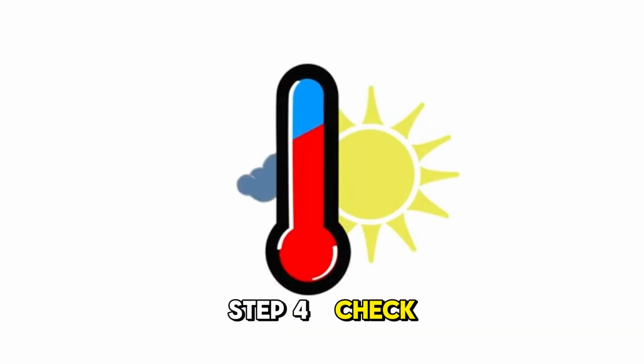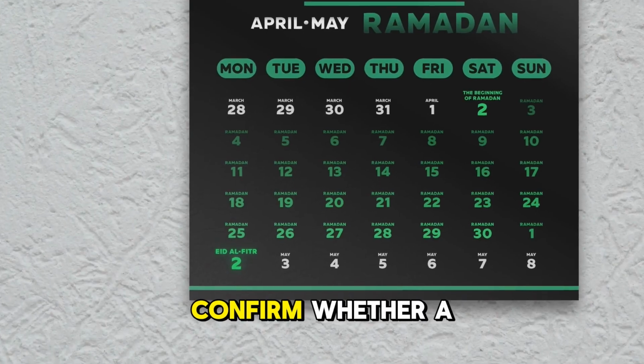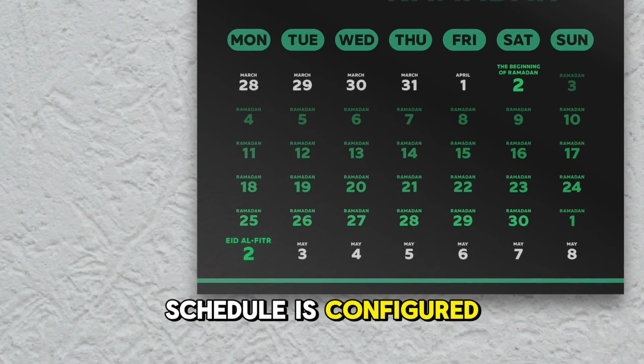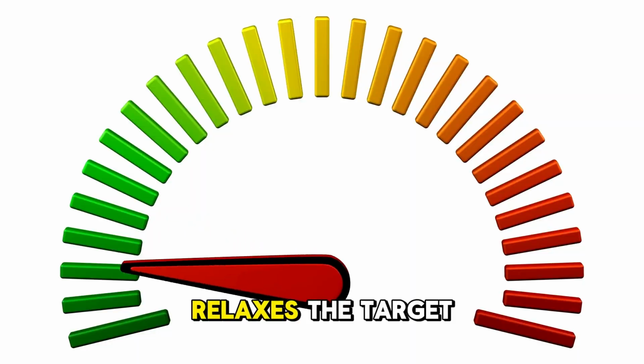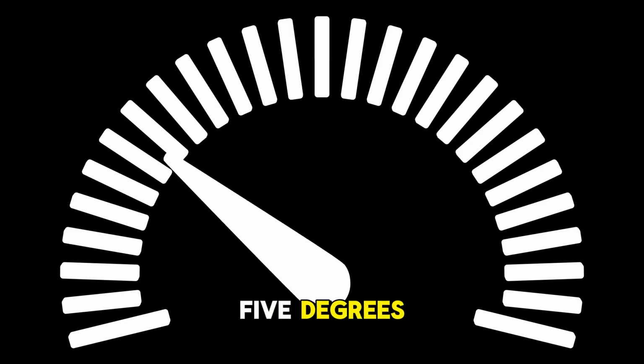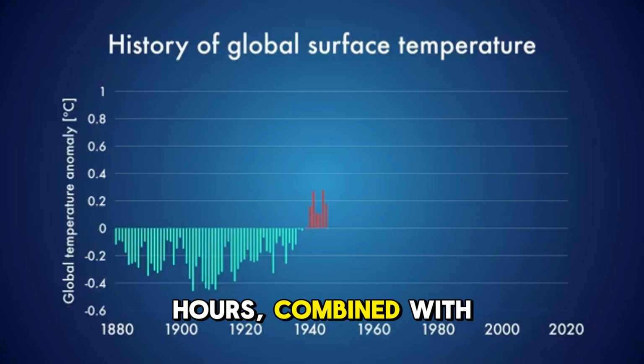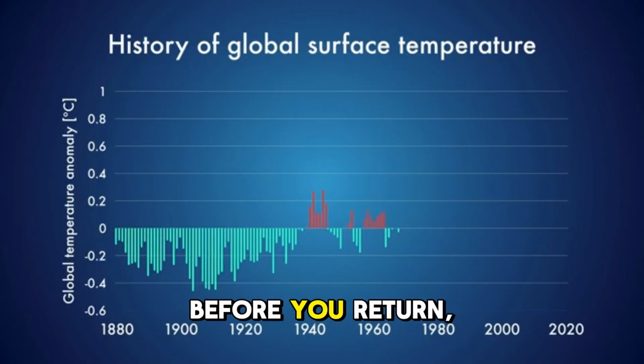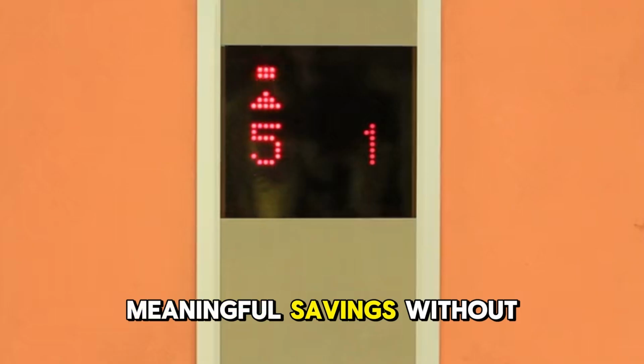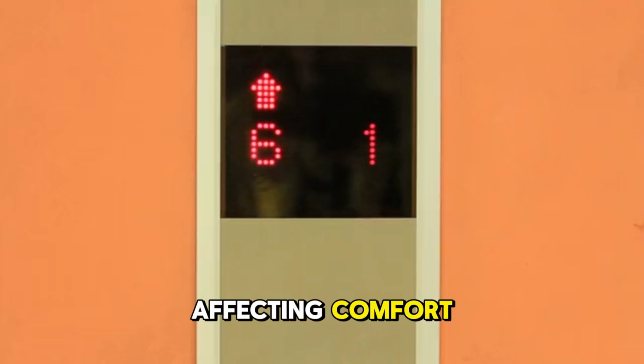Step 4. Check your cooling schedule. Confirm whether a schedule is configured. A schedule that relaxes the target by 3 to 5 degrees during unoccupied hours, combined with a recovery ramp before you return, adds meaningful savings without affecting comfort during the hours you actually feel it.